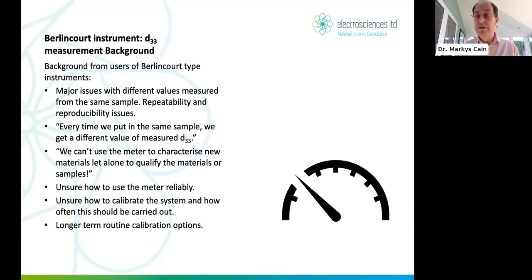You put the sample in once, take it out, put it in again, you get a different answer. I mean, you shouldn't; you should get the same answer. The sample hasn't changed, or, you know, has it? I mean, theoretically it hasn't changed, but more of that later. Every time you put the same sample in, we get a different value of measured d33. We can't use the meter to characterize new materials, let alone to qualify the materials or samples.